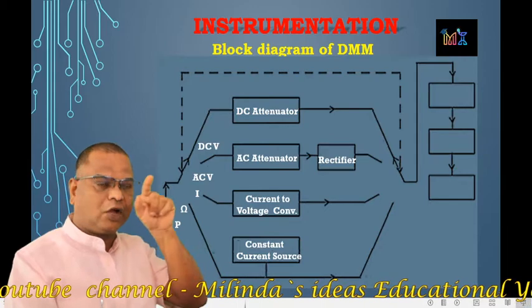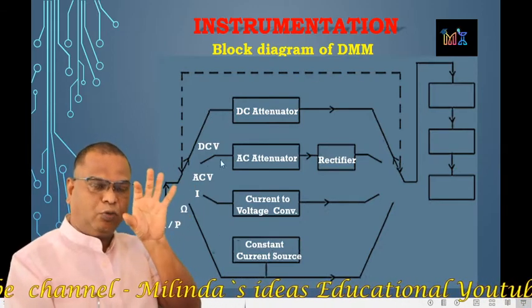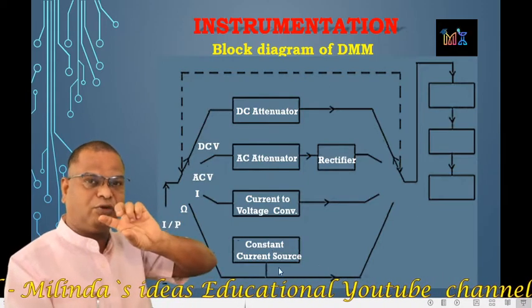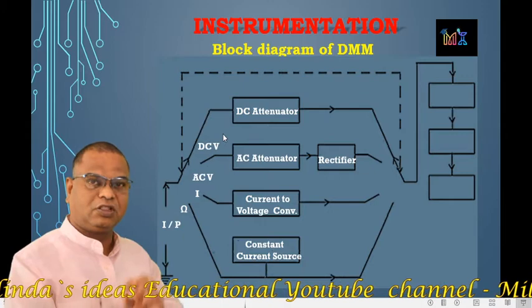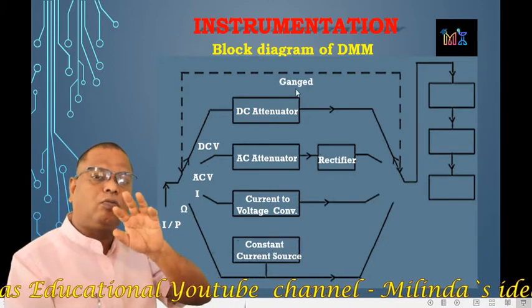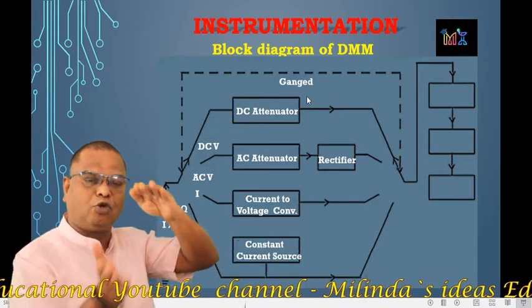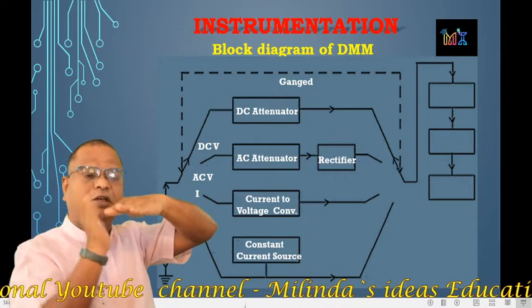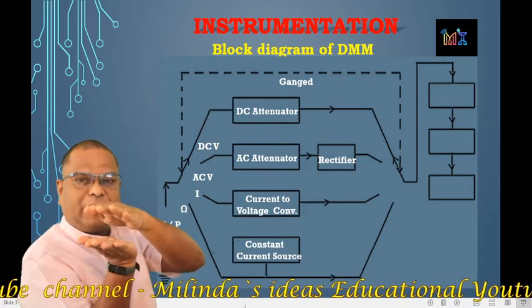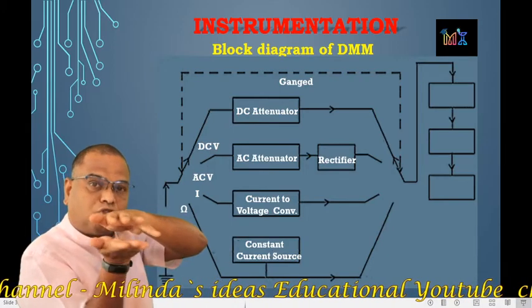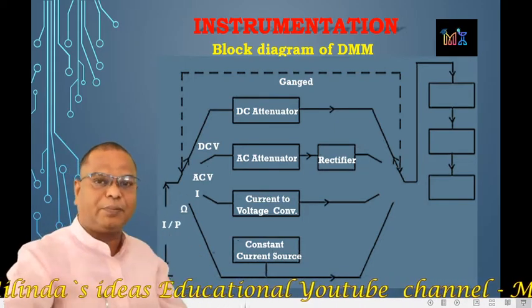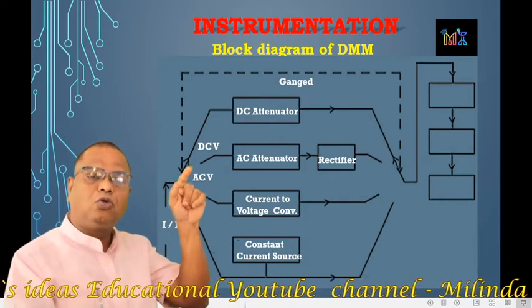The dotted line is connected to the output switch. There is an input switch and an output switch — they are ganged, meaning by using a single knob we control the position of two switches. The two switches are connected to a rotary switch, and that rotary switch is connected to another rotary switch. The output of each attenuator block is connected to the A to D converter. Suppose we are going to measure DC voltage, so the output of the DC attenuator should be connected to the A to D converter.